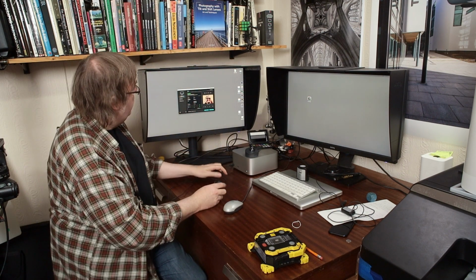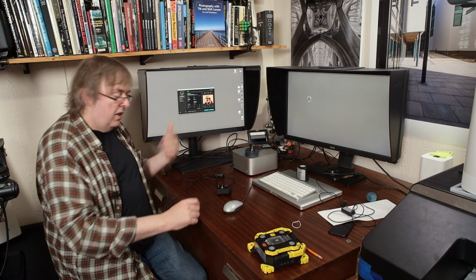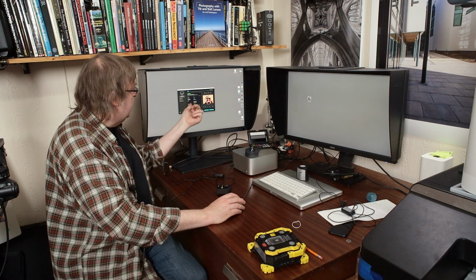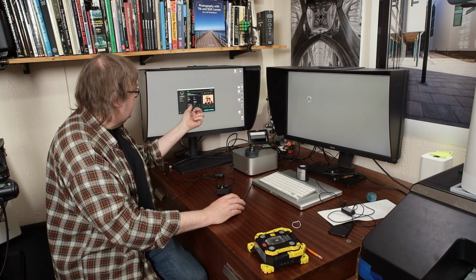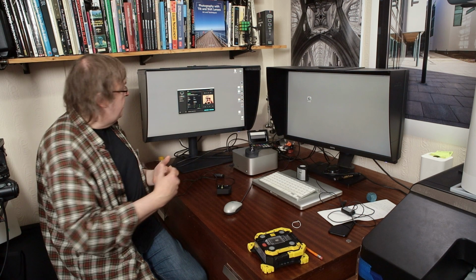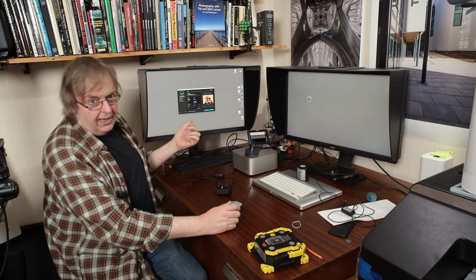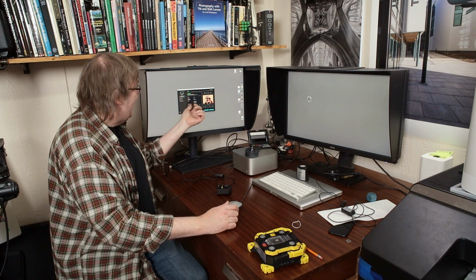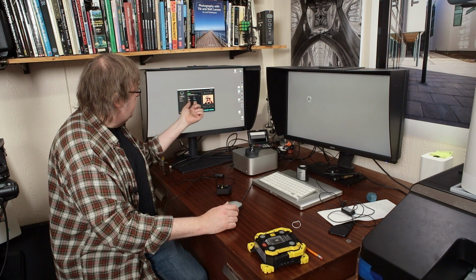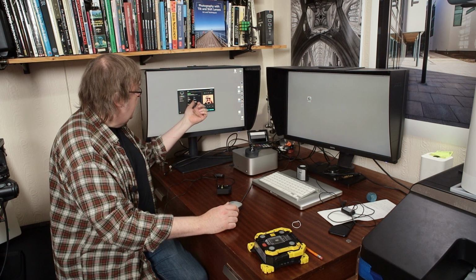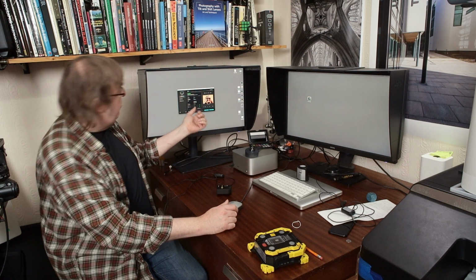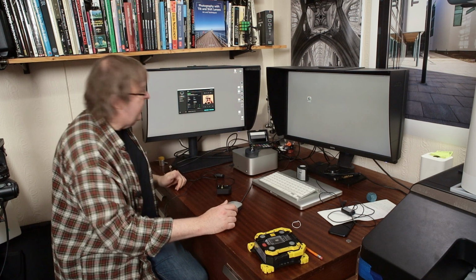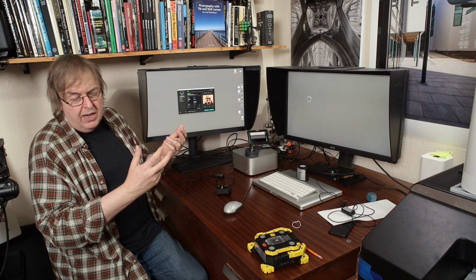Put the cover back on it. We have an example photo so we can see there are before and after options. I can see that I've asked it to calibrate to 120 candelas per square meter. It has done. I've set it to 4000 and the actual measured value from it is 4058. You'll often get a bit of variation in these numbers. Don't be worried by it.